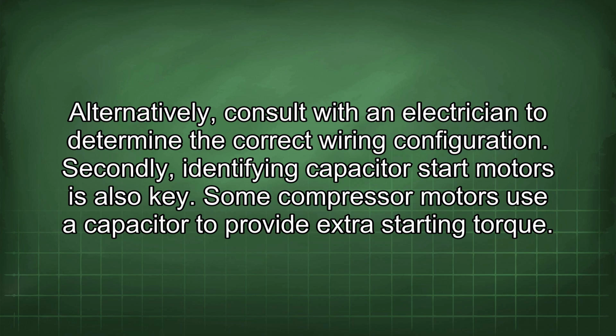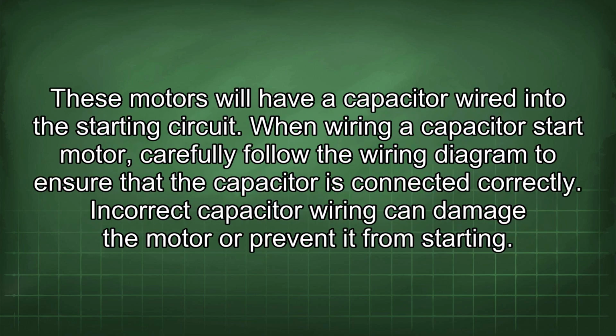Secondly, identifying capacitor start motors is also key. Some compressor motors use a capacitor to provide extra starting torque. These motors will have a capacitor wired into the starting circuit. When wiring a capacitor start motor, carefully follow the wiring diagram to ensure that the capacitor is connected correctly. Incorrect capacitor wiring can damage the motor or prevent it from starting.